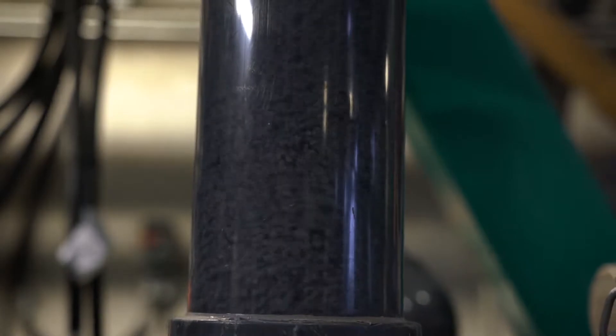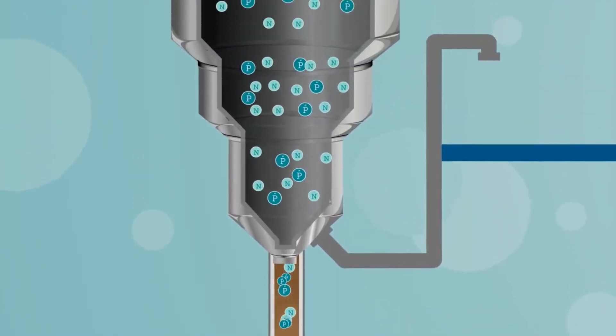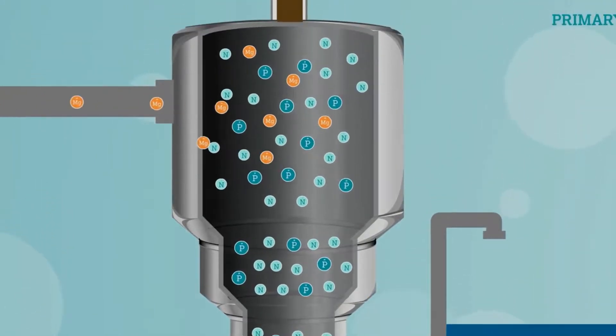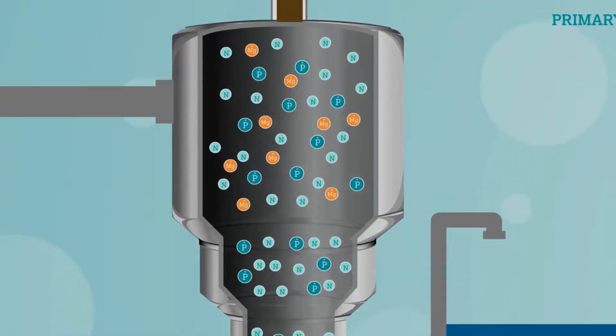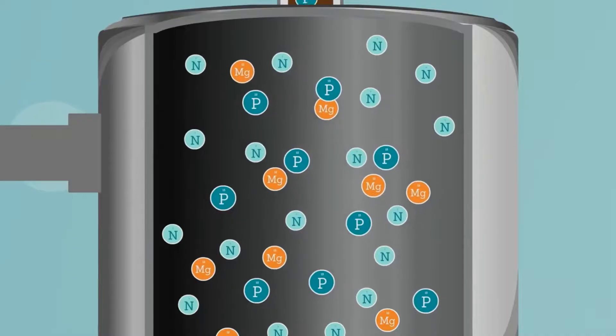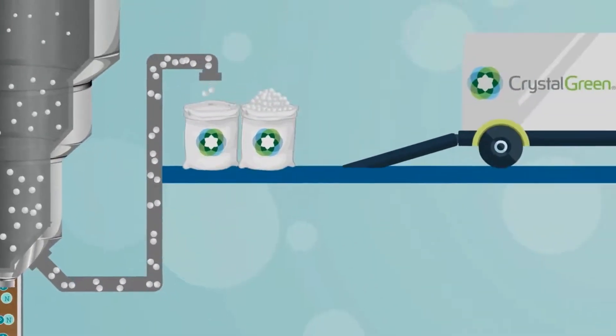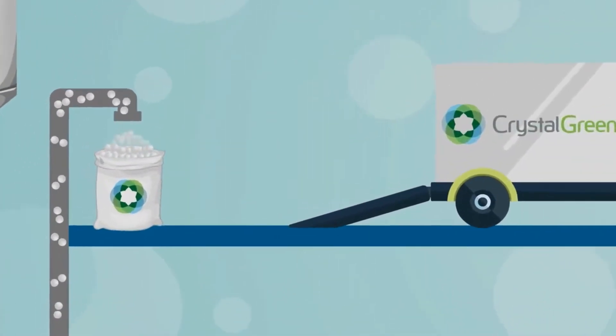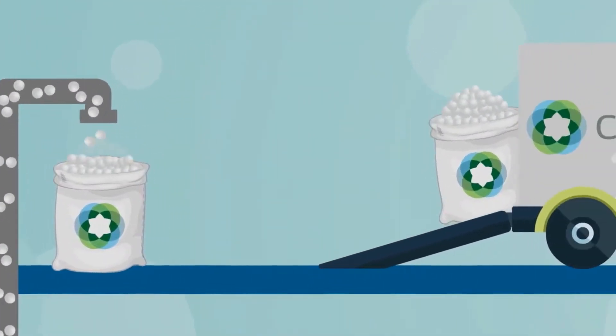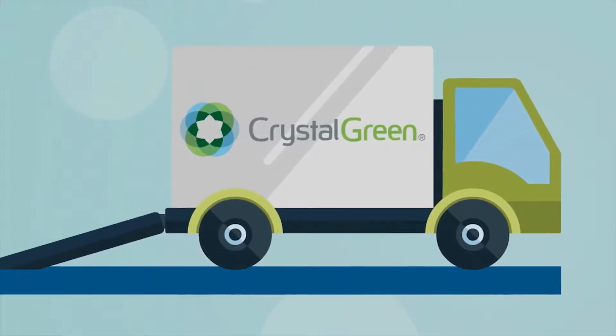The system intercepts the recycle flow and recovers phosphorus before it has a chance to cause operational problems. Magnesium is added, pH levels are calibrated, and when the resulting crystals are ready, they're harvested, dried, bagged, and distributed. The prills are a key element in Crystal Green, an all-purpose fertilizer that can be used on just about anything.